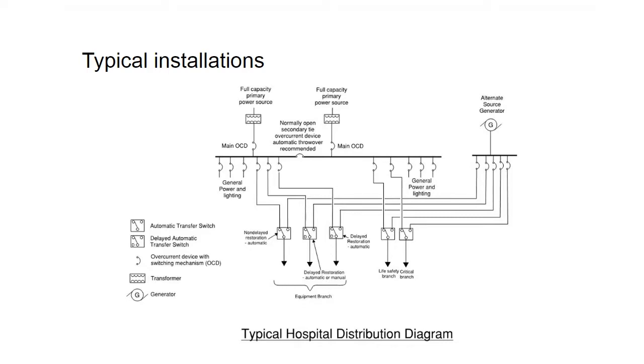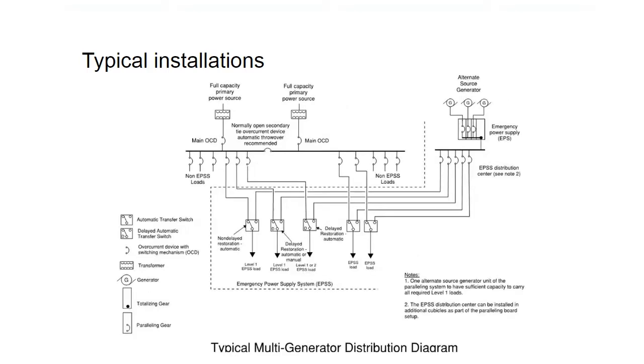So you're going to see some images here, some typical slides or typical distributions. So here, the normal power redundancy, you're looking at dual sources. I mentioned you want to start at that side of the equation, ensure that you've got reliability there through dual sources, a main-tie-main arrangement, ideally even with automatic transfer capabilities on that side. Again, with multiple transfer switches.